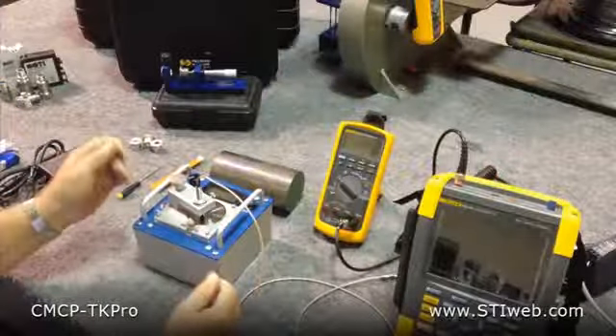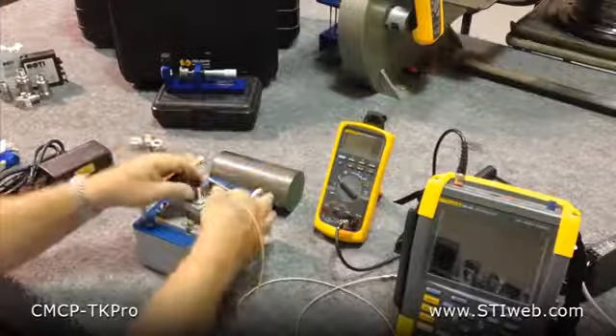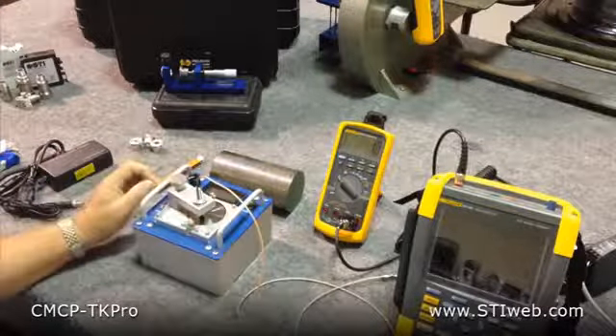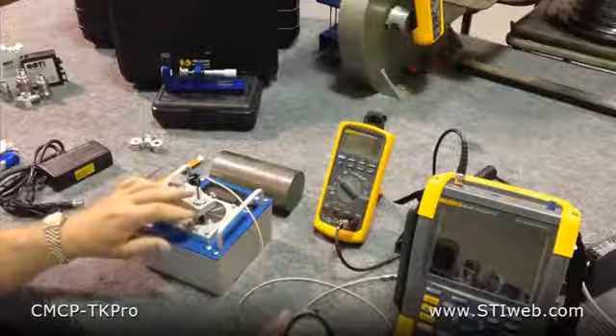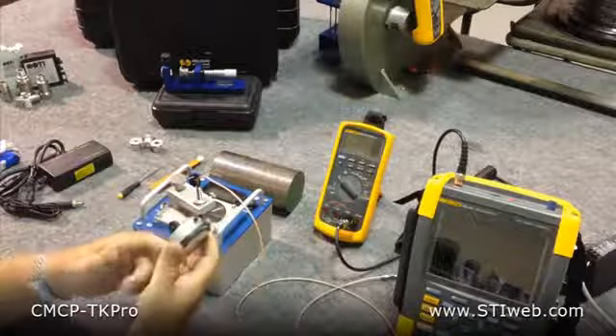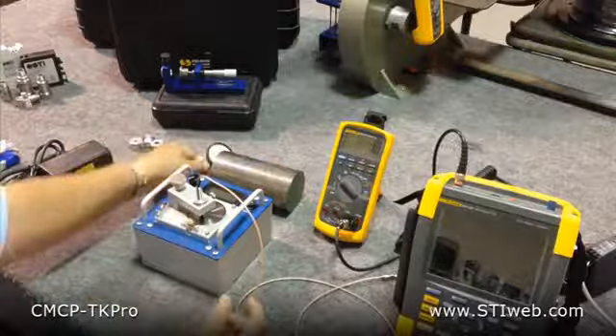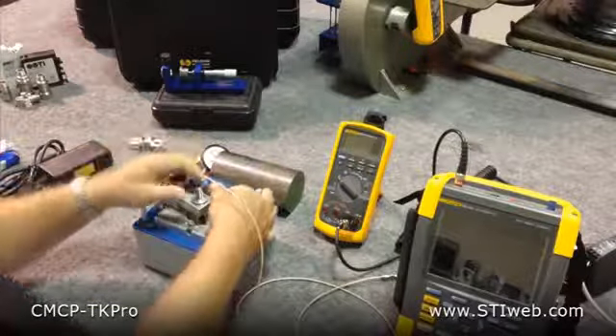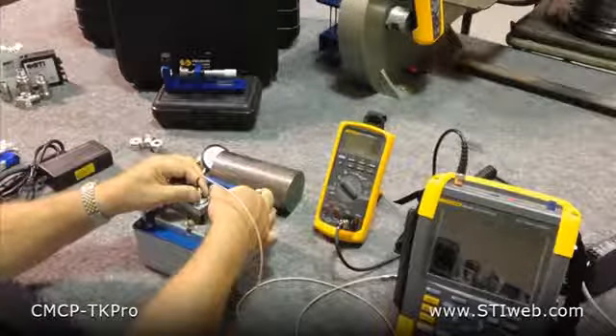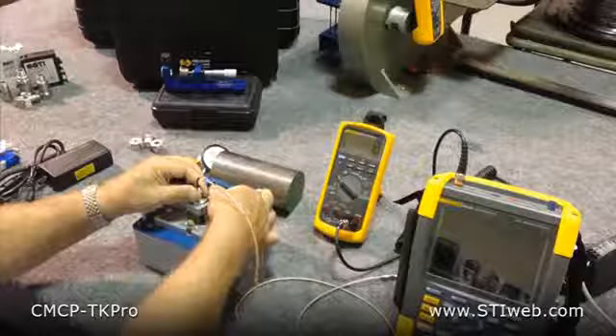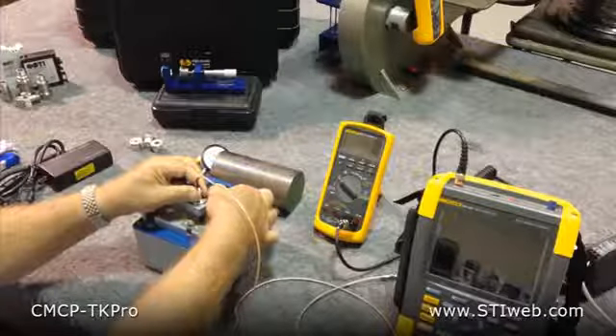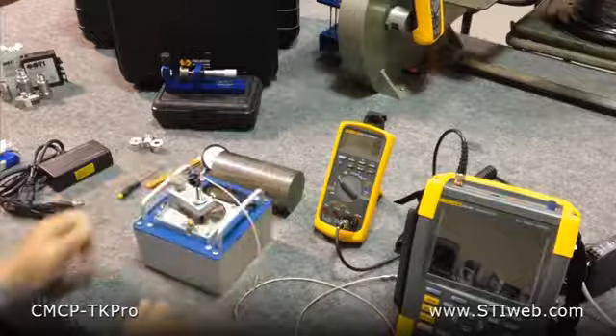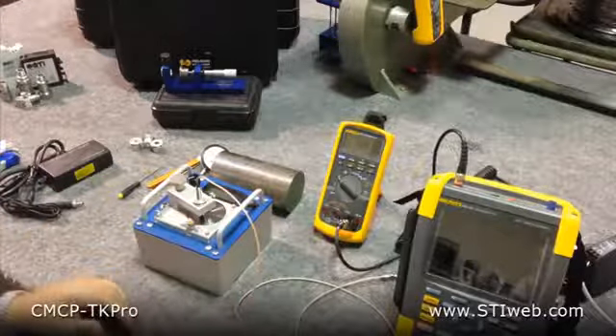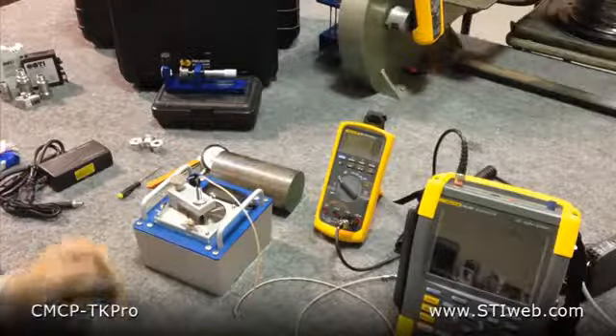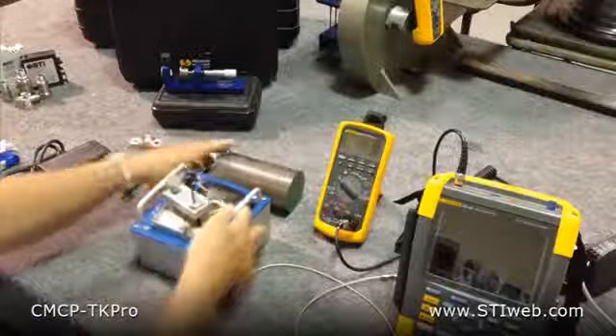Okay, what we're going to do now is gap the probe. We've installed the probe, and it's the same collet we used for the dial indicator because the 3/8-24 probe uses the same 0.375 collet. And now we're going to gap the probe to about 10 volts. We do that by simply screwing it in and out a little bit. So that's fine right there. That's a decent gap, 10.82 volts, as you can see on the voltmeter. Now we're ready to run our test.